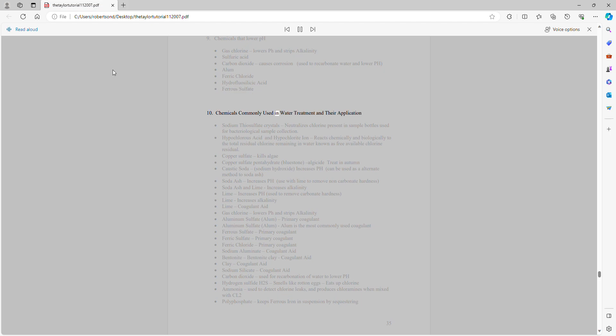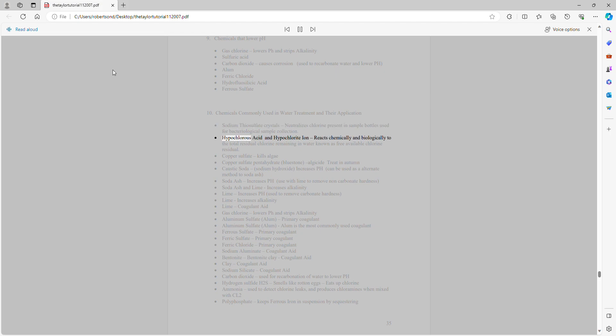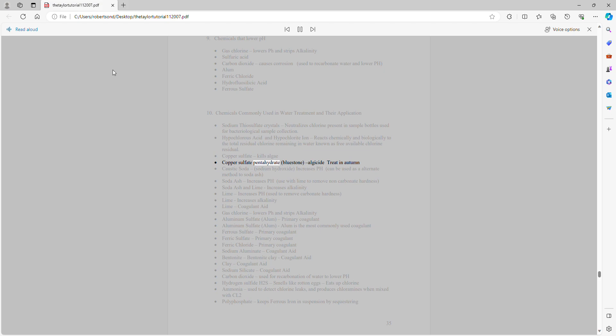Chemicals commonly used in water treatment and their applications: Sodium thiosulfate crystals neutralize chlorine present in sample bottles used for bacteriological sample collection. Hypochlorous acid and hypochlorite ion together make up the total free available chlorine residual. Copper sulfate kills algae (also called copper sulfate pentahydrate or bluestone). Algaecide: treat in autumn. Caustic soda (sodium hydroxide) increases pH and can be used as an alternate method to soda ash.